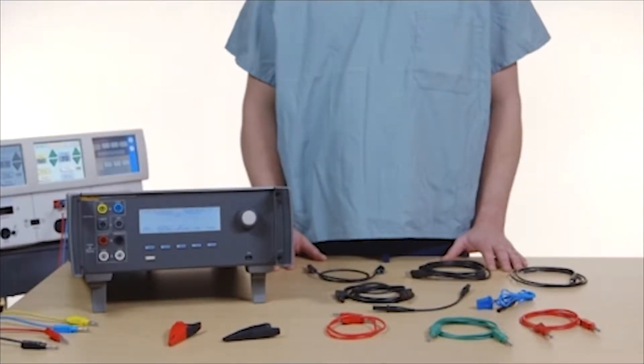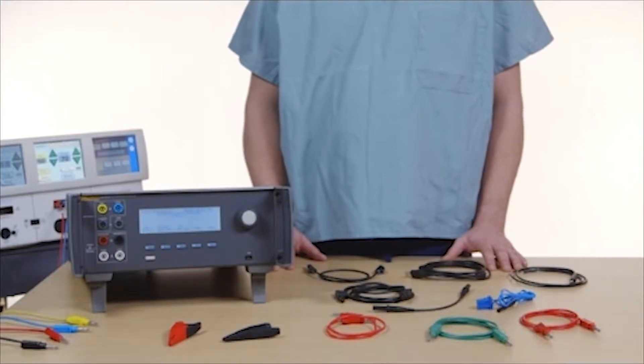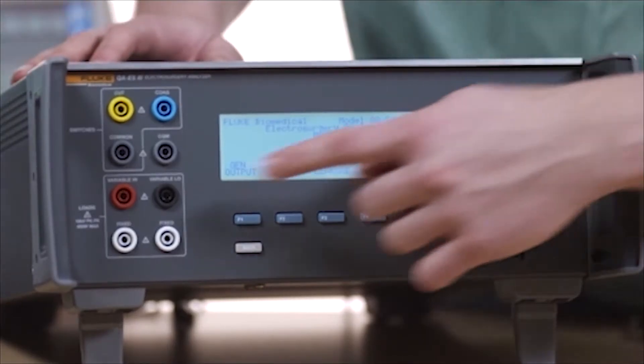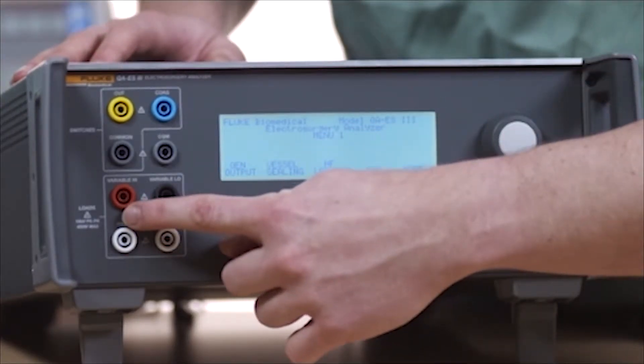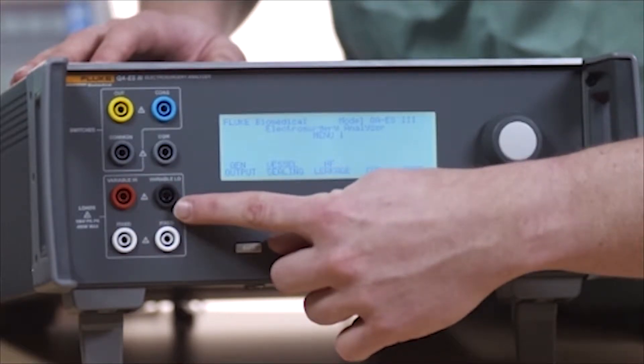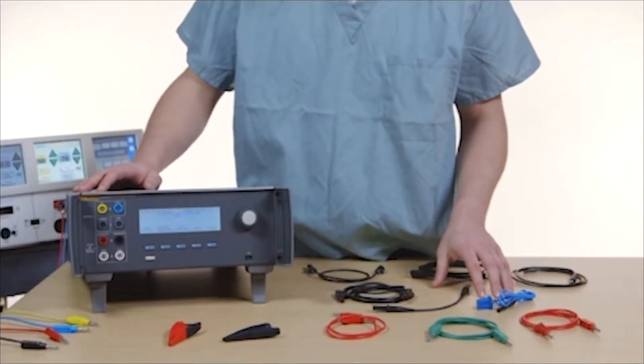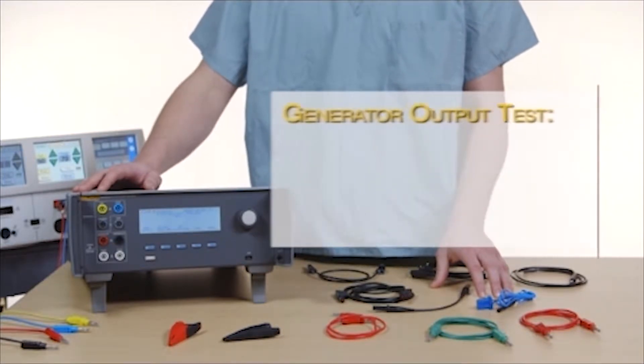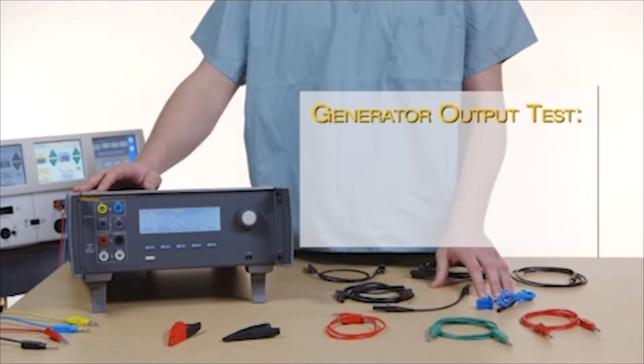During the generator output test, the QAES3 connects the variable load resistance from the variable high-active electrode to variable low-neutral electrode.